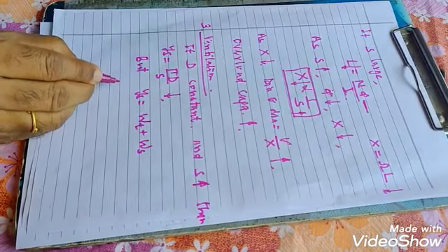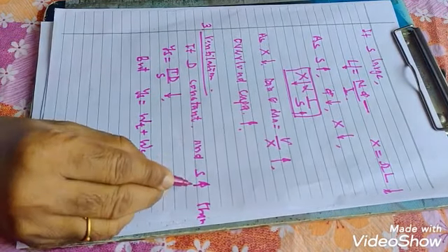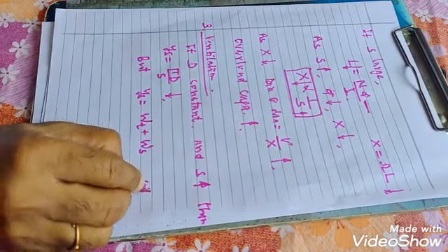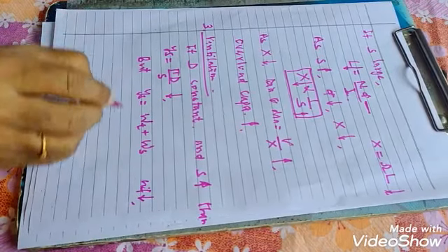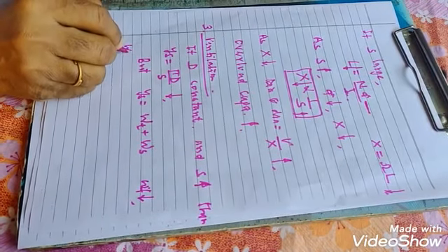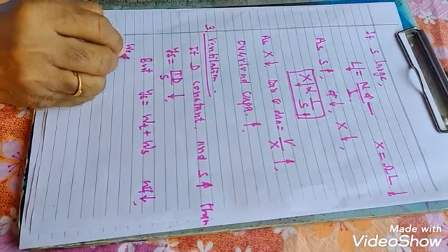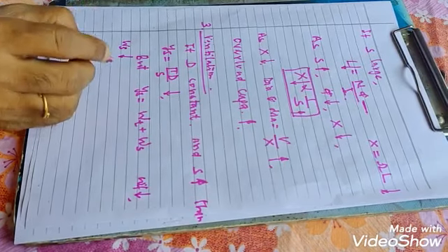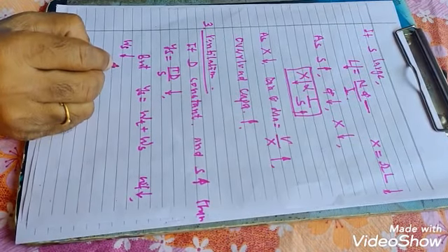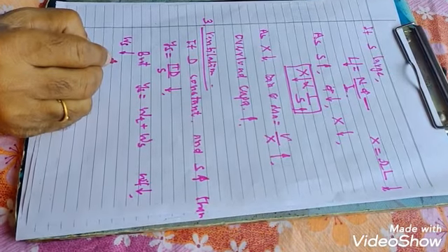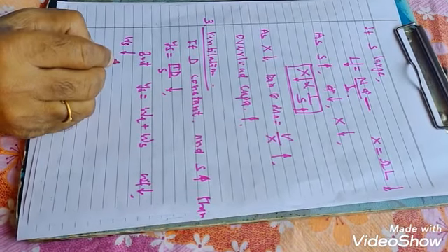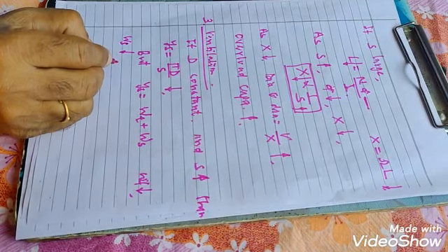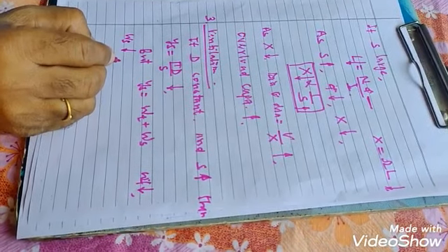So if YS decreases because of a large number of slots and constant D, the width of slot and the width of teeth both decrease. So the teeth become mechanically weak, and may be supported by welding on the ventilating duct. That affects the cooling.